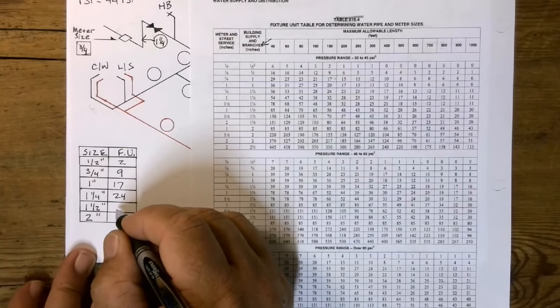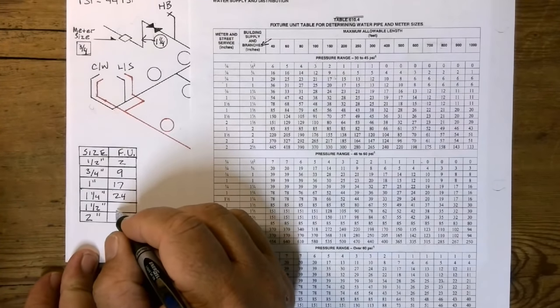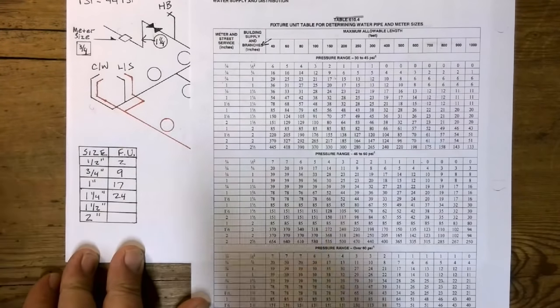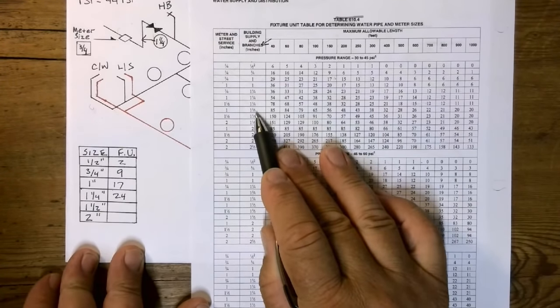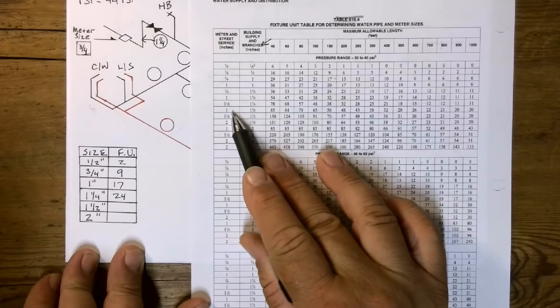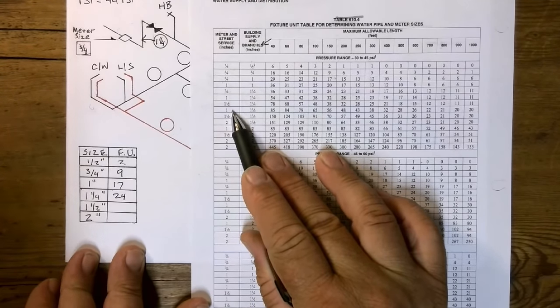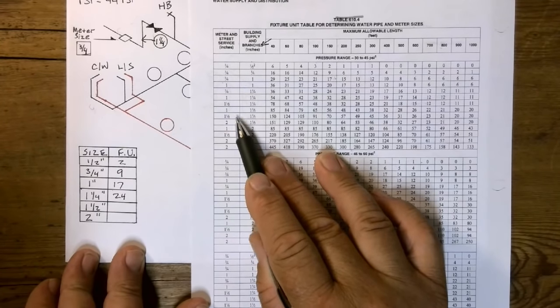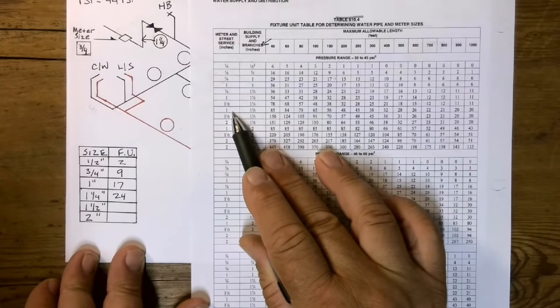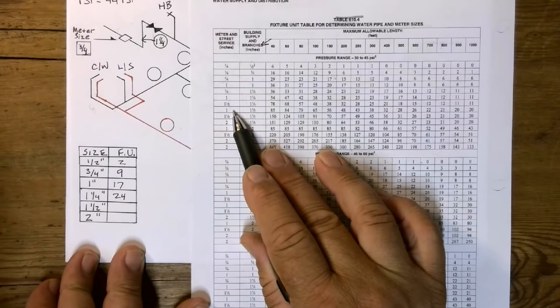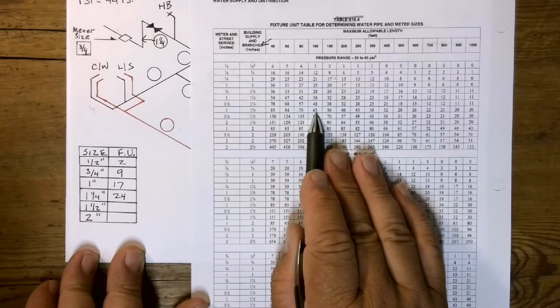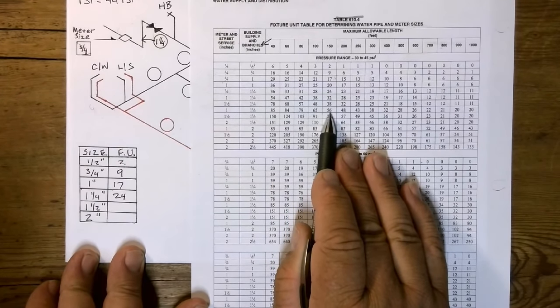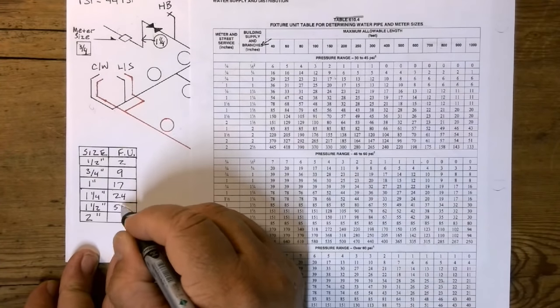And then the 1½, if you want, we can go ahead and do 1½, it doesn't bother me. So you go to 1½, you see 1½ is written 3 times, but check this out. The lowest meter is 1 inch, then it's 1½ meter, and then it's 2-inch meter. So guess what? You just go to the lowest meter because it's the closest one to 3/4. And at that 1½, it's going to be 56 fixture units. So you can write 56 in here if you want.